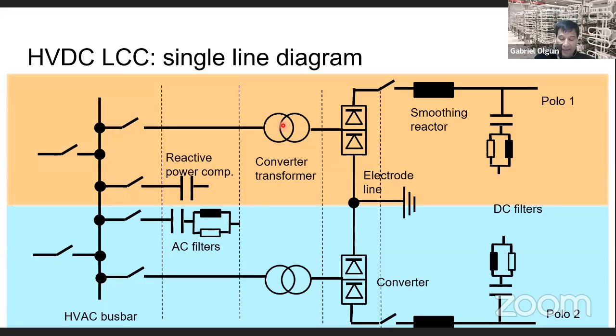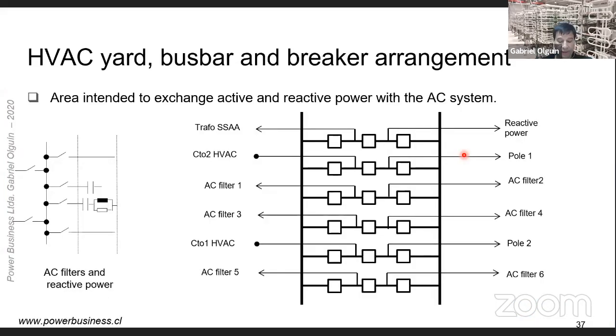A very basic line diagram of a bipolar LCC converter station is shown in this slide. Main components of the converter stations are the HVAC bus bar arrangement, the reactive power and filters in the AC side, the converter transformer, the valve hall, and the HVDC yard. Let's review some of these areas of the converter station. The HVAC yard, the bus bar and the breaker arrangement.